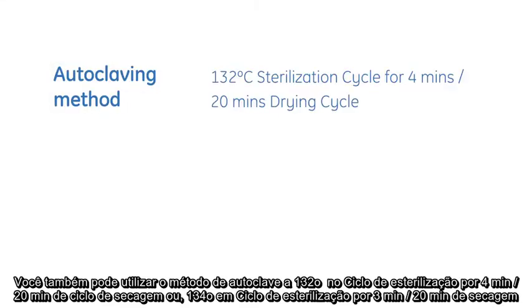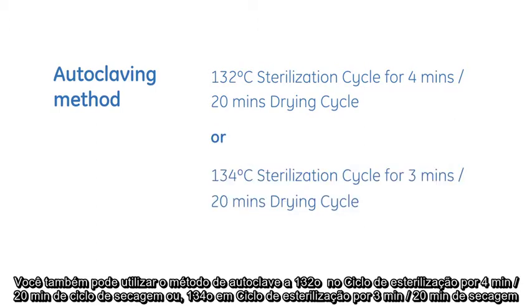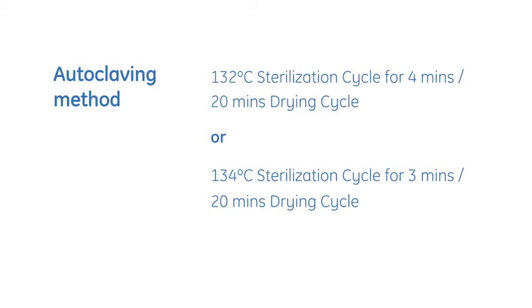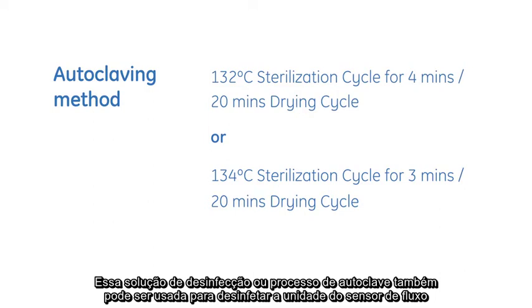You can also do autoclaving at a 132-degree sterilization cycle for 4 minutes, 20 minutes drying cycle, or a 134-degree sterilization cycle for 3 minutes, 20 minutes drying cycle. This disinfecting solution or autoclaving process can also be used to disinfect the neonatal flow sensor.